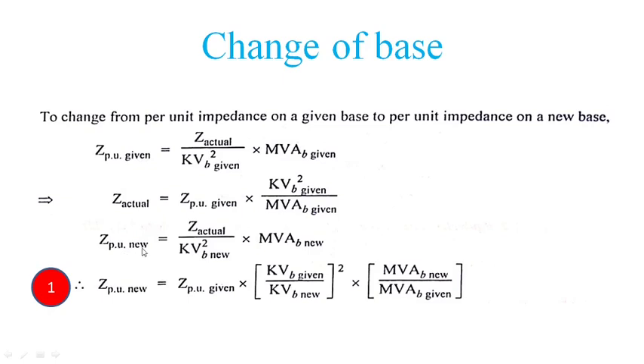That's all. So Z per unit new is equal to, there is no change in the actual value. The actual value is the same, which is given for any equipment. Actual values are not changing, only per unit values are changing because of the change in the base values. Because we know that per unit value is equal to actual value divided by base value. So there is no change in actual value, only the base is changing. So this Z actual is also the same value. So Z per unit new is equal to Z actual into MVAB new divided by kVB new square.